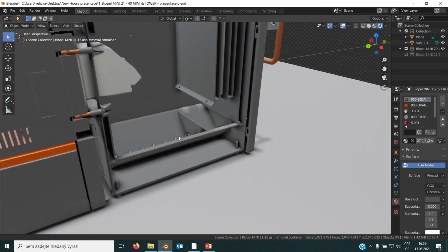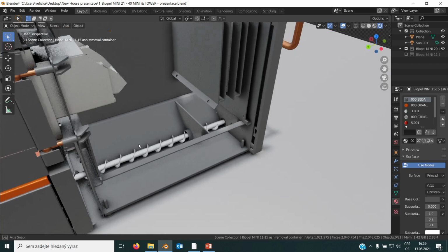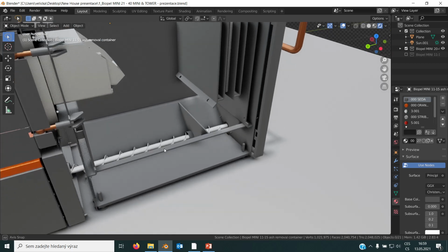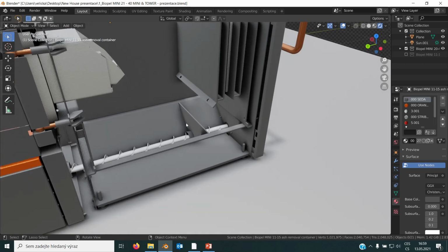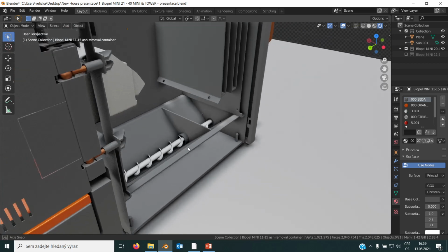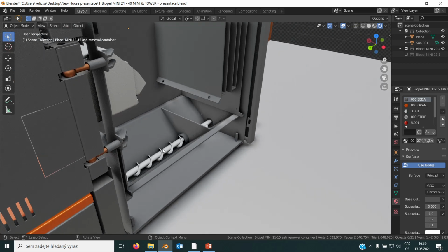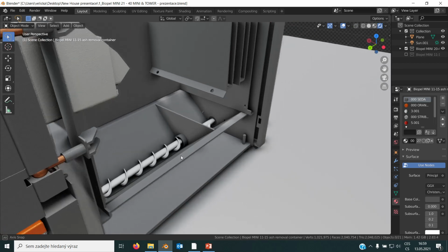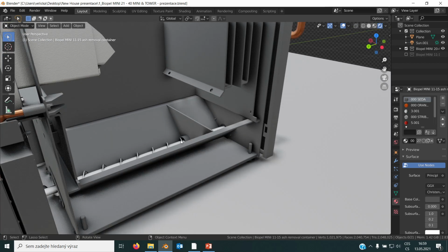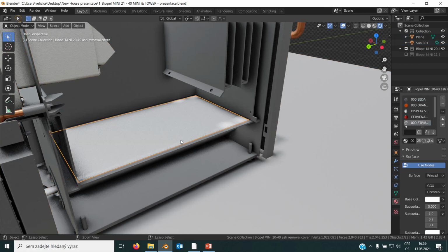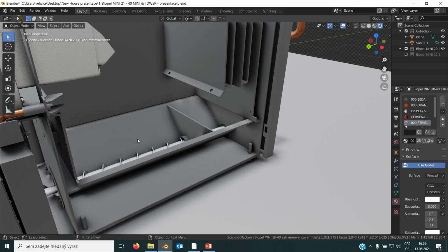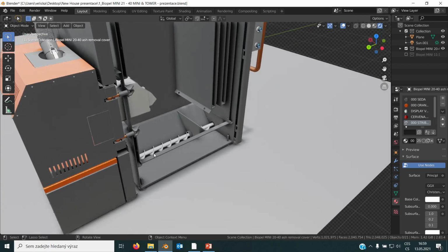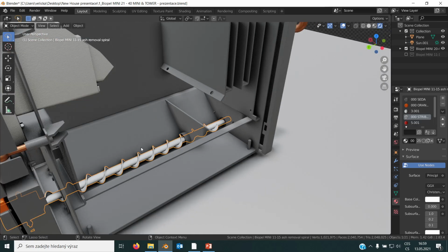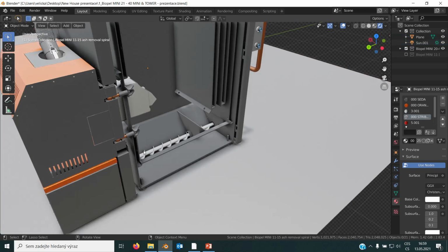But with the V9 Premium, this section was separated. You had to install a new ash container with these plates directing the ashes to the spiral. Right now with Biopel Mini, everything is inside the boiler, so you just remove this plate, and then the boiler is ready for ash removal. Of course, when you install the spiral with the motor and with the ash box.